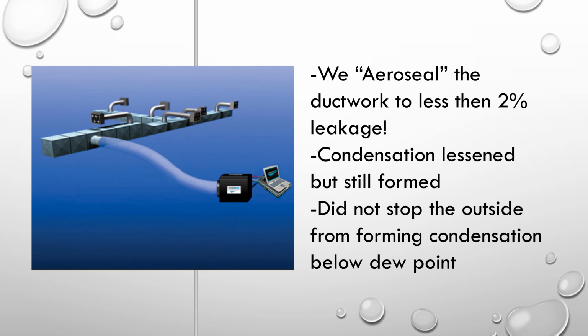We went ahead and Aerosealed this duct system and got down to 2% leakage. So that's a sealed duct system. North Carolina State Code is 5%, but we got down to 2%. The condensation did lessen, but it still formed. It did not stop the condensation from forming because the outside of the ductwork was still 68 degrees.